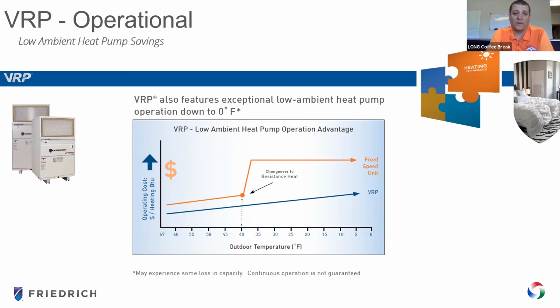With the VRP, you're also able to take heating all the way down to 0. So we have plenty of days here in Colorado where we're sitting below 40, and typically in most systems we'd be kicking on electric heat. It works fine, but just the efficiency of electric heat is not nearly that of a compressor. So by being able to have the compressor continue to provide heating all the way down to 0, you're able to still see those efficiency savings while maintaining a comfortable environment.